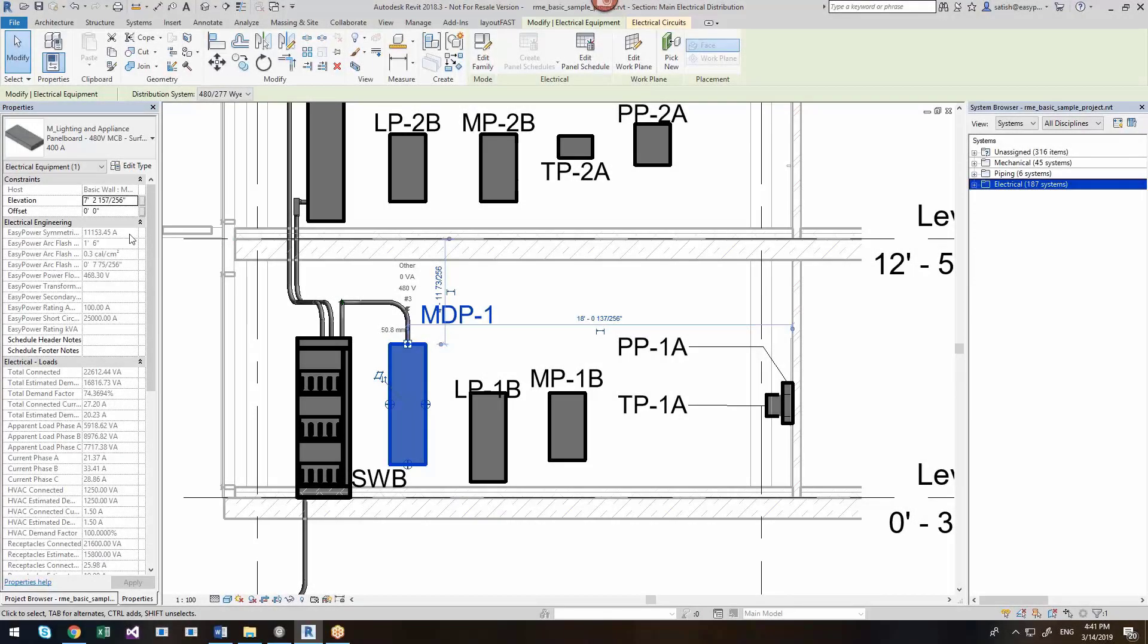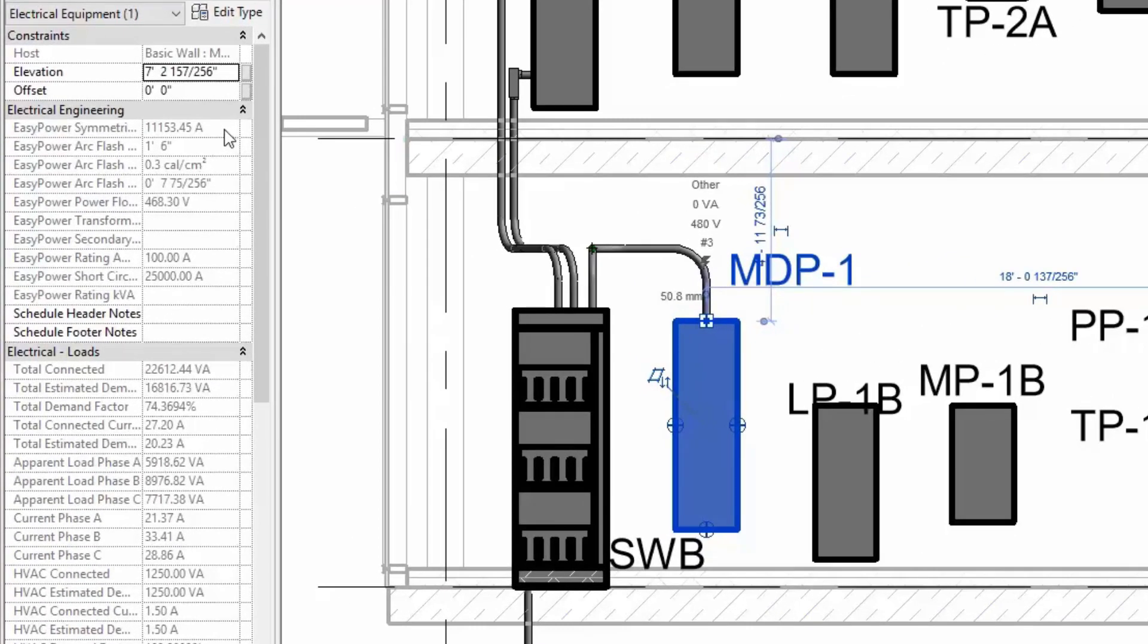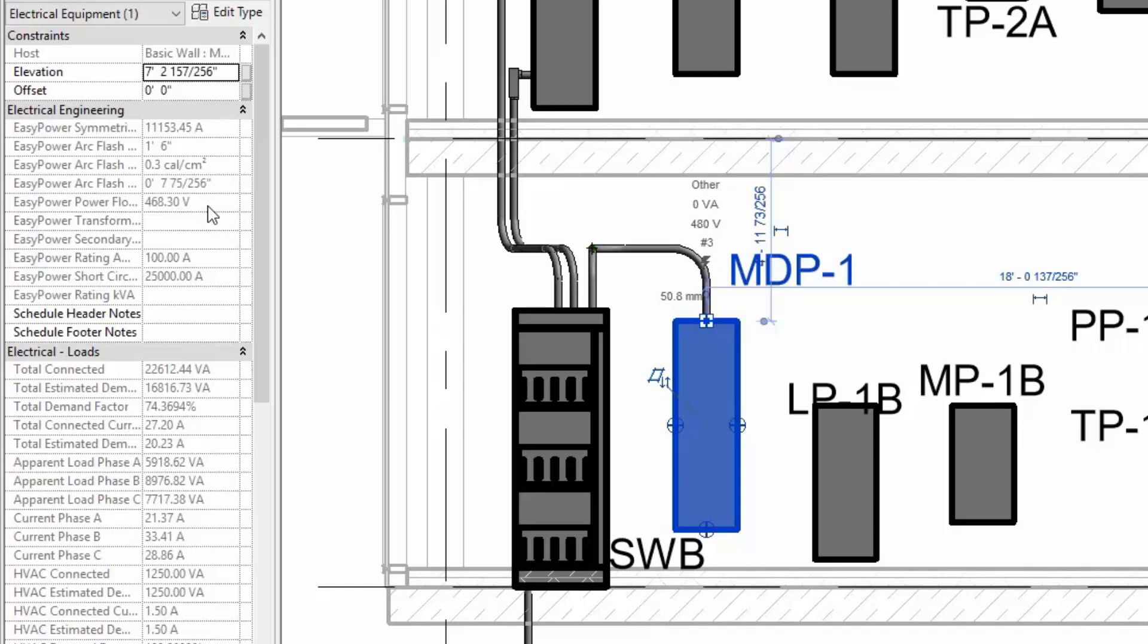Here, we see the fault currents, the working distance for the incident energy calculations, and the arc flash boundary. It shows the voltage that is calculated for a load flow or power flow calculation. It also gives you a short circuit rating for the equipment.